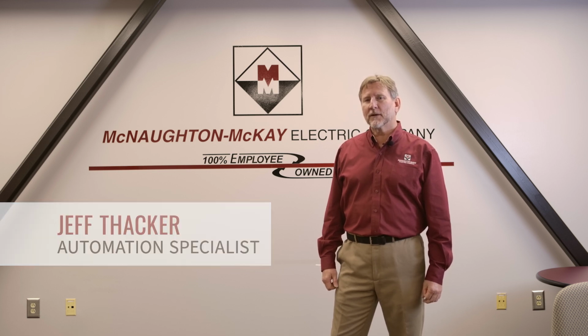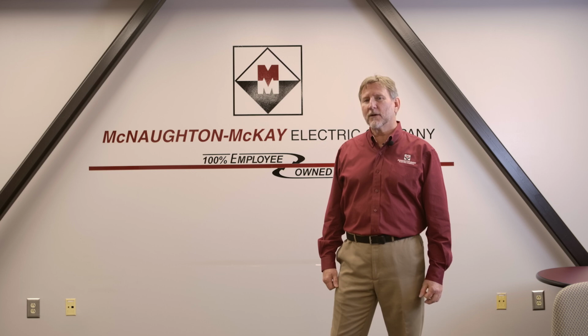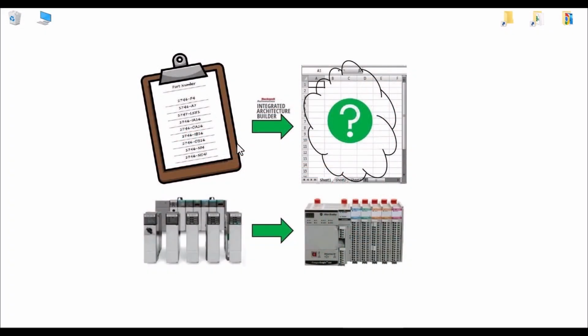Today I'm going to talk to you about utilizing Integrated Architecture software for SLC 500 to CompactLogix hardware migrations. So the goal is to migrate an obsolete SLC 500 system to a new CompactLogix. We would begin by itemizing the individual SLC components and use Integrated Architecture Builder to automatically develop an Excel spreadsheet of the CompactLogix components. Here we have a 5/05 processor, AC input and output module, DC input and output module, and analog input and output module.